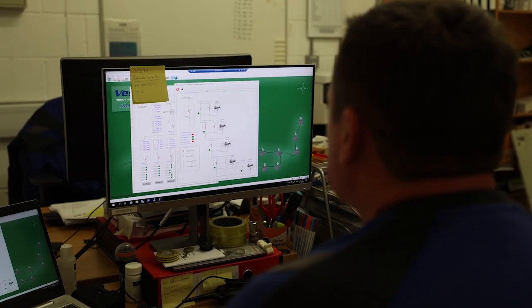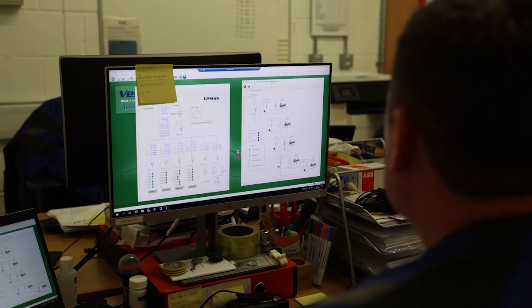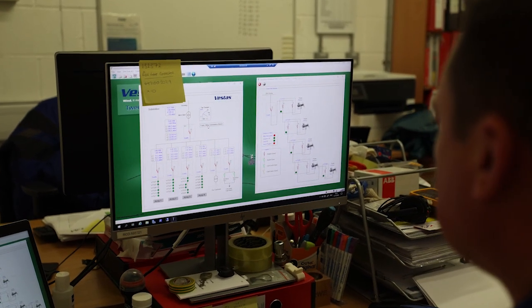So is there anything else we should be aware of when accessing the area near high voltage switchgear? A lot of the equipment is automatically or remotely controlled. This means any problem on the network could result in something operating while we're in there. When nearby switchgear operates without warning, it can be quite a shock to the system. But if this happens or you find any other problem with the switchgear, you should leave the turbine and alert the control room, who will contact our high voltage colleagues.